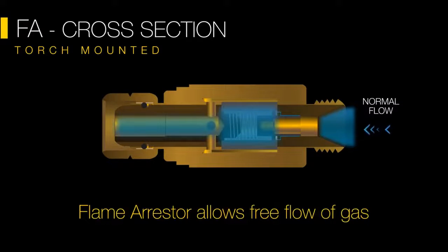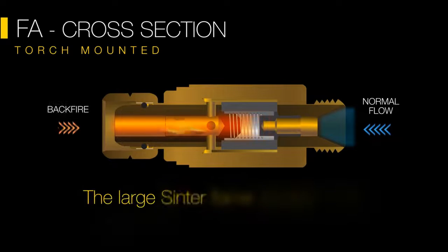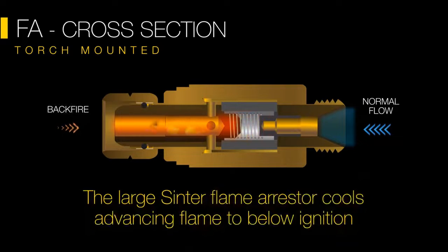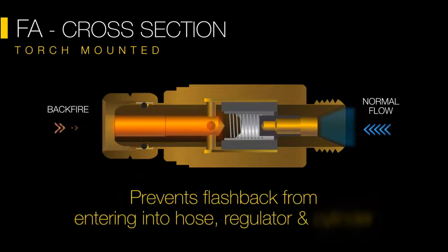The sinter flame arrestor allows free flow of gases with minimal pressure loss. It cools the advancing flame to below ignition temperature. The arrestor prevents the flame from spreading into hoses, regulators, and cylinders, helping to prevent major fire accidents.